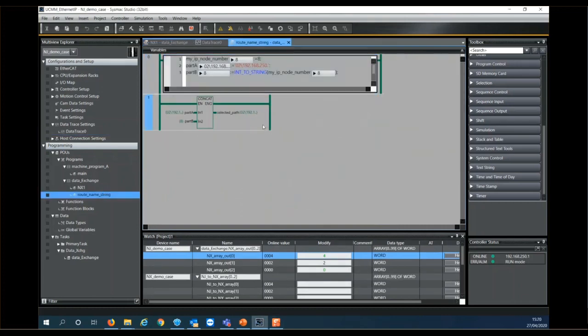So something very useful with this method of exchanging data over the EtherNetIP facility is that we can, inside the program, retain the EtherNetIP connections. And inside the program, we can also change them. So we could effectively set the network up from the program or from the HMI. So that gives us an option to connect machines together programmatically and even by the operator, which is something that tagged data links wouldn't allow us to do. So here we can see the use of a concat just to explain how that might be done.